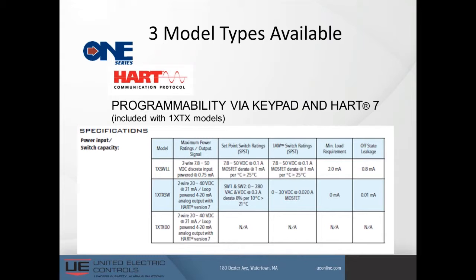So the next device that you see on this spreadsheet is basically the 1X TX SW. What that is, is the same device that we saw above, but now this device has two switches in it. You remember before you would have thought of it as the 8W. The 8W is gone. It's the 1X TX SW. What this is, is a loop-powered two-wire transmitter. It's a 4 to 20 milliamp transmitter. It houses two switches, switch 1 and switch 2. If you don't want to use the switches, we'll talk about that, but if you want to just use one switch, use one switch. You want to use both switches for high-high, high-low capabilities, it's in here.